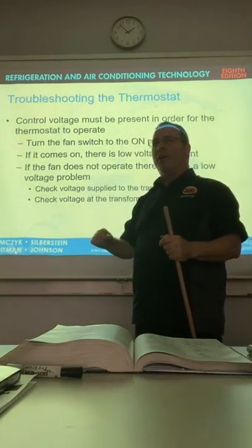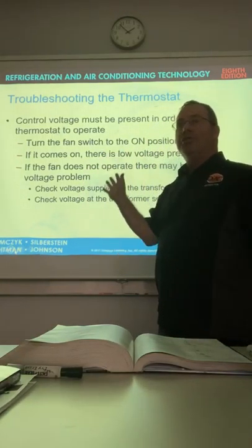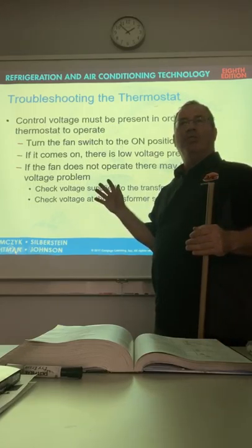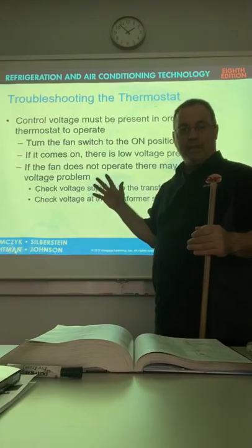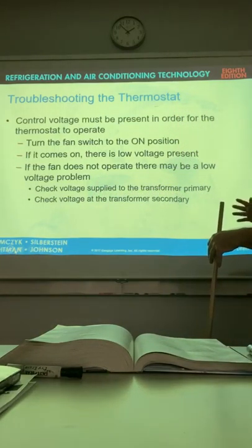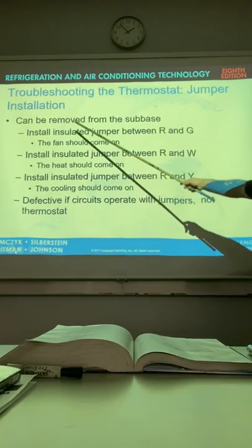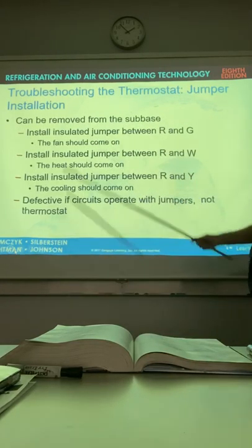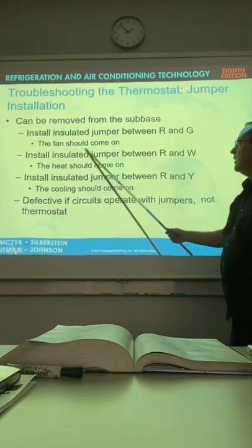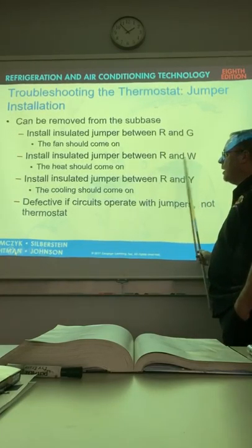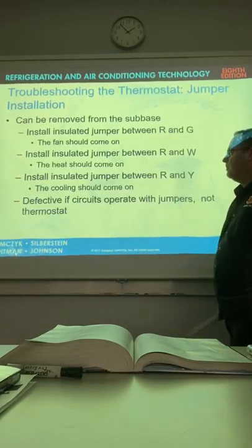Control voltage must be present in order for the thermostat to operate. Turn the switch to on. If it comes on, the low voltage is there. So, any time you walk in the house and you turn the thermostat on and you hear the blower come on, you've just eliminated the whole concern of not having low voltage. That's all working. If the fan does not operate, it may be a low voltage problem. Check voltage to the transformer.